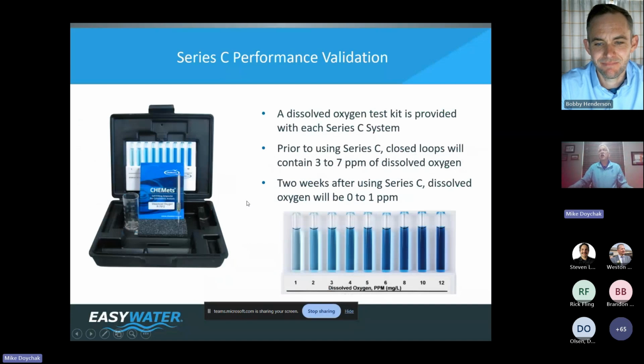Dissolved oxygen. We want you to know how you know this thing's working. Obviously, it's a closed loop. You can't just look inside there. We want you to know it's working with every single system that we send out. We send a dissolved oxygen test kit, and we ask you to do this simple instruction. Prior to using our Series C, test your loop. What you're going to find is the dissolved oxygen is going to be up near this top here. The glass ampoule is going to be dark blue, indicating some level of dissolved oxygen. 2 weeks or more after you install it, test it again, and you will see you will be down to the lower end of the scale, indicating dissolved oxygen has been removed, and that means corrosion has been removed.